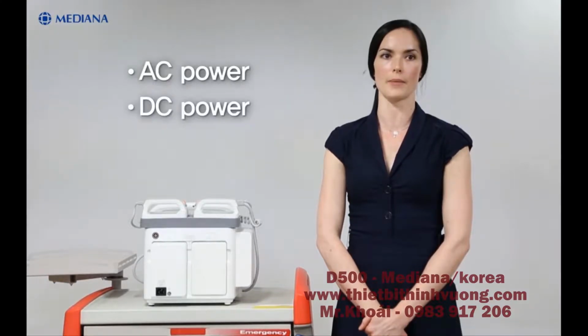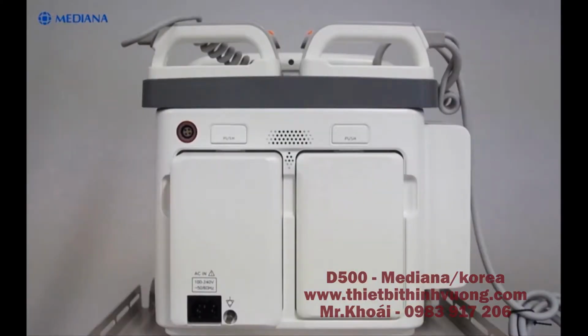Now we will go through the power supplies and how to use them. You have 3 different types of power supply: AC power, DC power, and battery. First of all, for the AC power, make sure that the AC outlet is properly grounded and supplies the specified voltage and frequency. After you plug the male type connector end of the AC power cord into a properly grounded mains outlet, please verify that the battery charging status LED and AC DC in LED on the D500's front panel are lit.